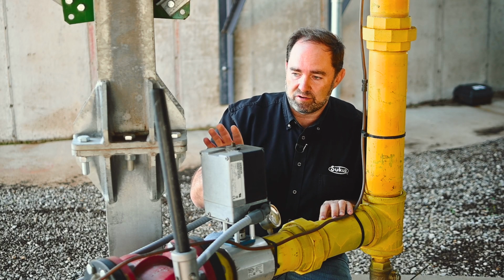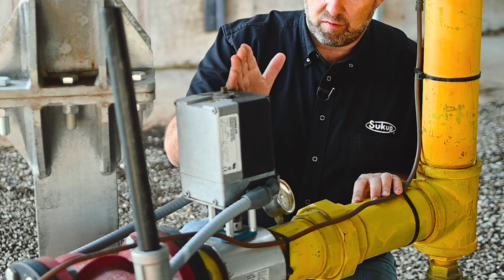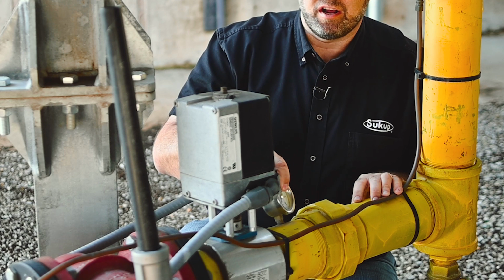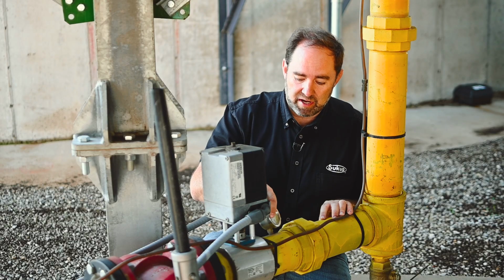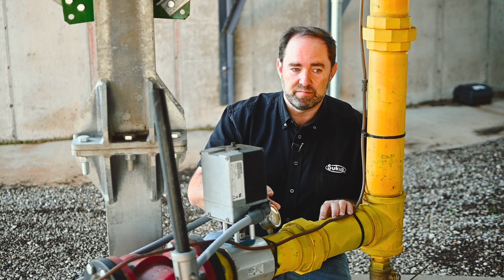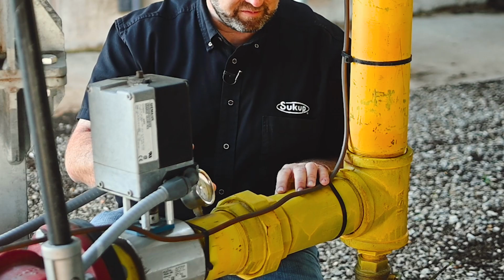And I mentioned the control regulator. With the butterfly valve wide open, we want to see 40 inches of water column on this gauge. Typically we're going to run at much less than that, but max would be 40, and that would be our set point. From there we come to a T.